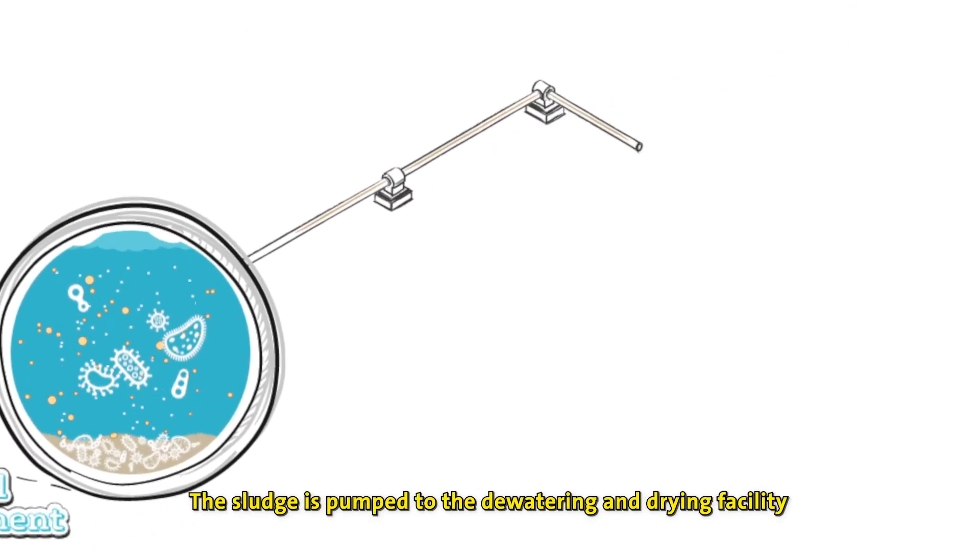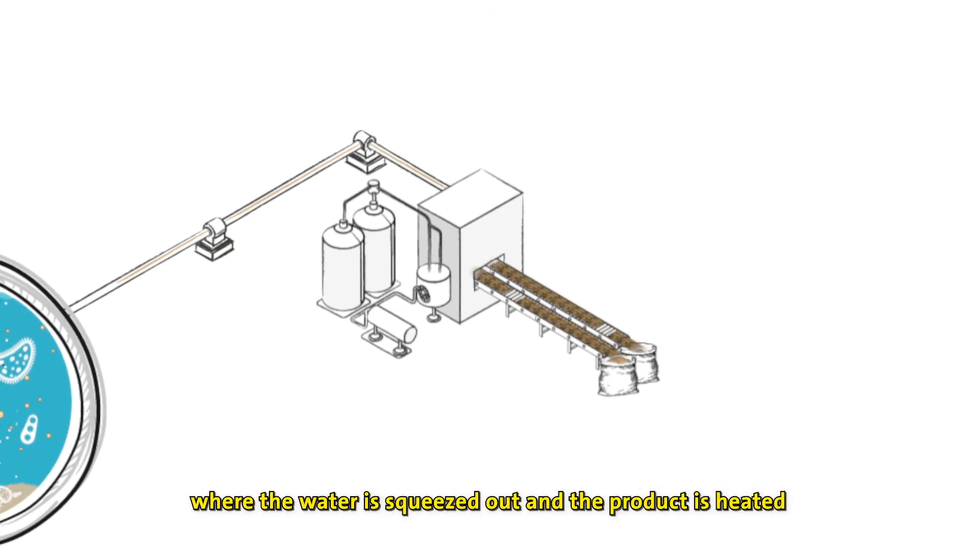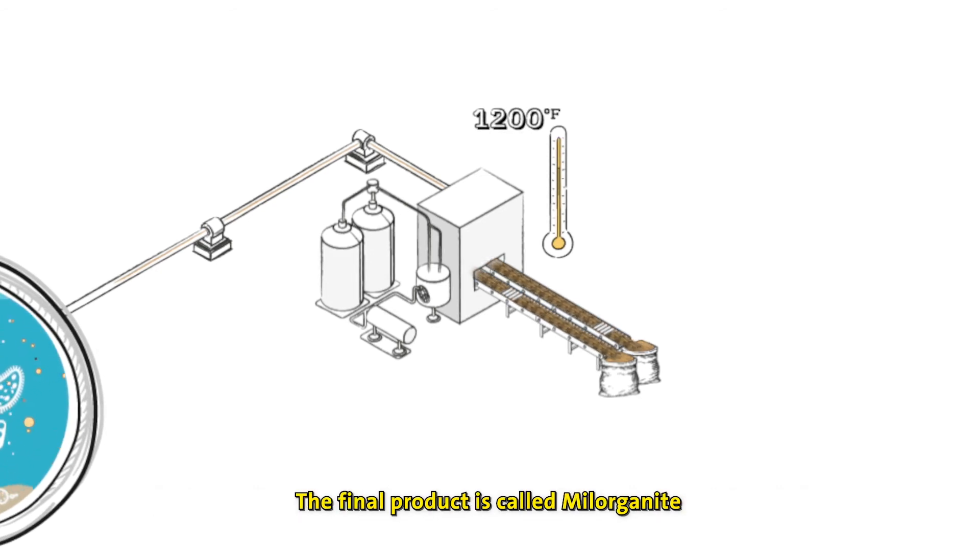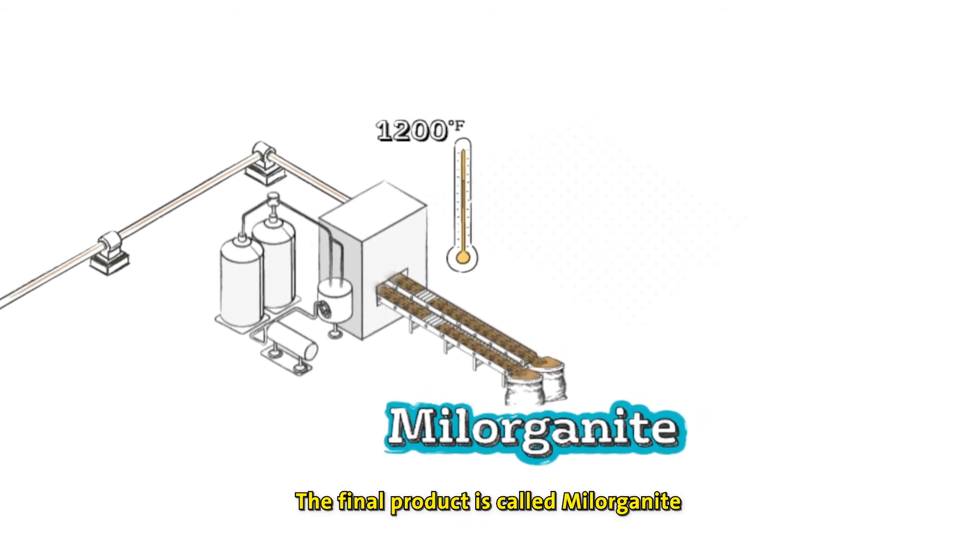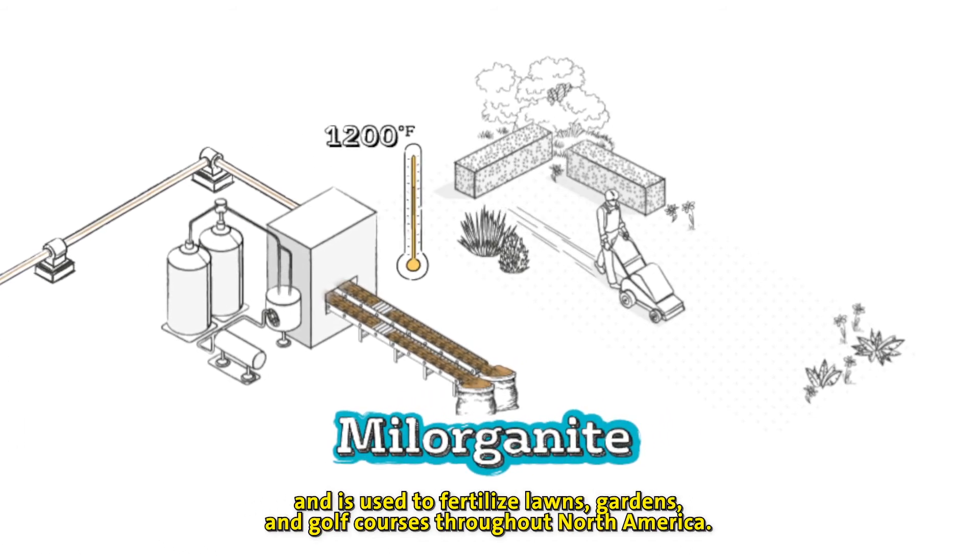The sludge is pumped to the dewatering and drying facility, where the water is squeezed out and the product is heated in dryers that can reach temperatures of 1,200 degrees Fahrenheit. The final product is called Milorganite and is used to fertilize lawns, gardens and golf courses throughout North America.